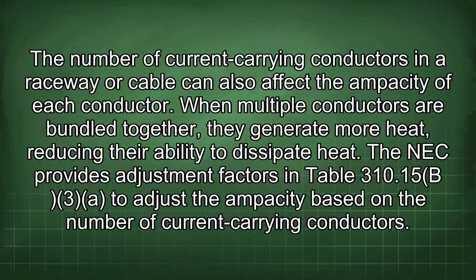The number of current-carrying conductors in a raceway or cable can also affect the ampacity of each conductor. When multiple conductors are bundled together, they generate more heat, reducing their ability to dissipate heat. The NEC provides adjustment factors in Table 310.15(B)(3) to adjust the ampacity based on the number of current-carrying conductors.